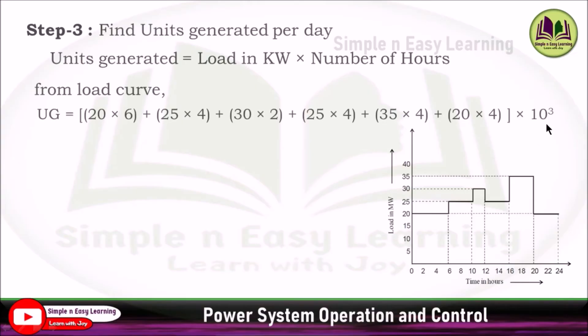Overall into 10 power 3. Why we need to put 10 power 3? Here the load is represented in megawatt, but in the formula, load in kilowatt times number of hours, the units generated will be represented in terms of kilowatt hour. That's why we are multiplying with 10 power 3. Units generated per day will be equal to 600 into 10 power 3 kilowatt hour.